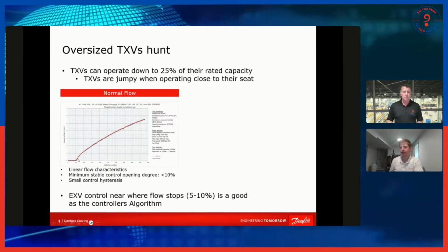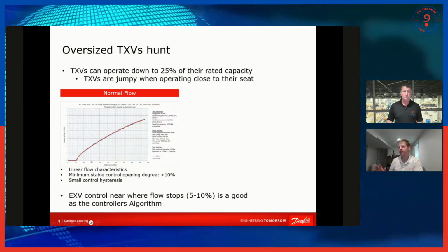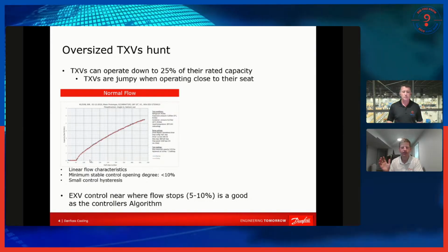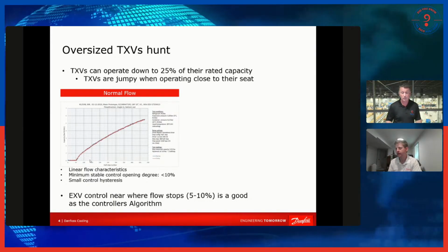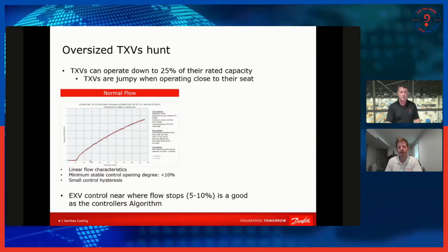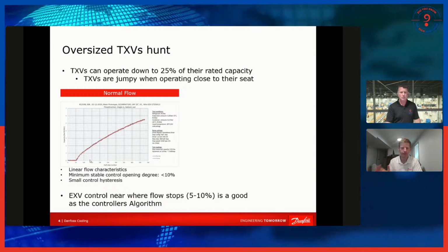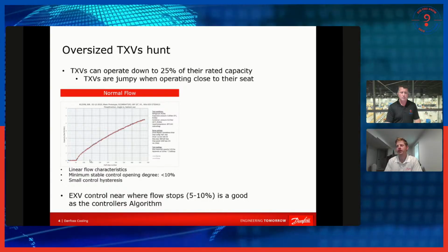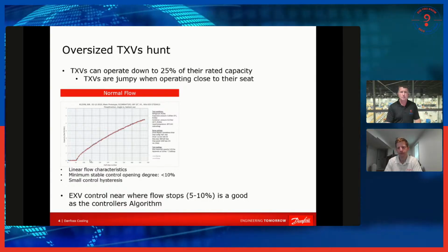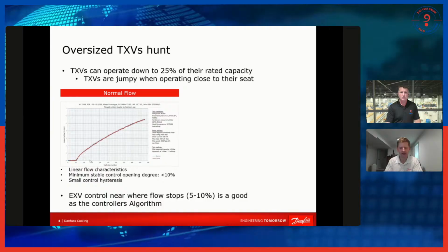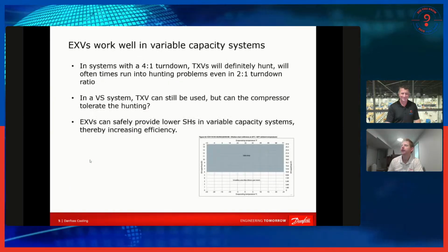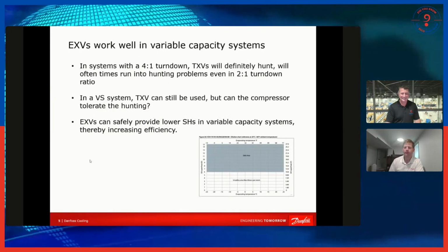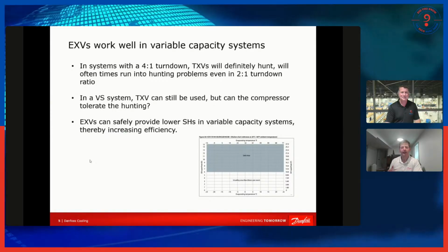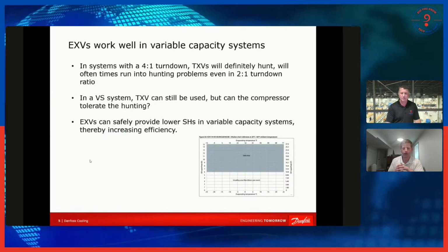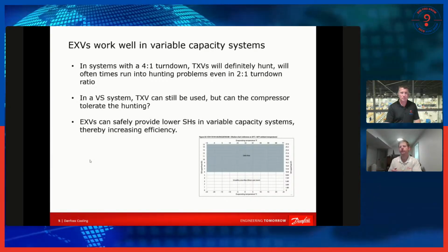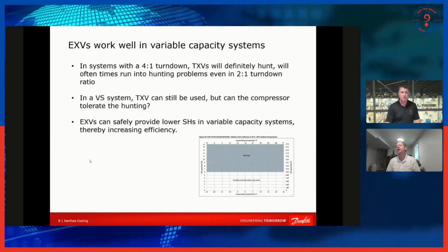EXVs typically have a pretty linear flow characteristic. They can control stably down to at least 10%, if not lower than that, of their rated capacities. And there tends to be very little hysteresis with them. So they can be very precise, assuming the algorithm that's set up to control them is well designed, well established, well tested. And this makes it so that EXVs work really well in a variable capacity system, whether it's a set of tandem compressors or a compressor with a VFD on it.